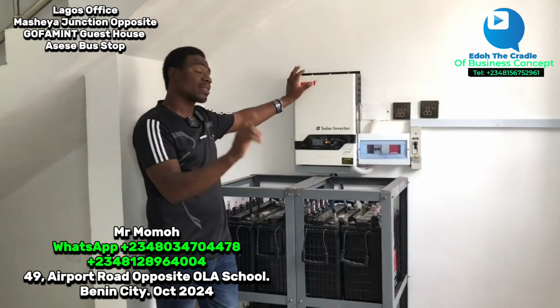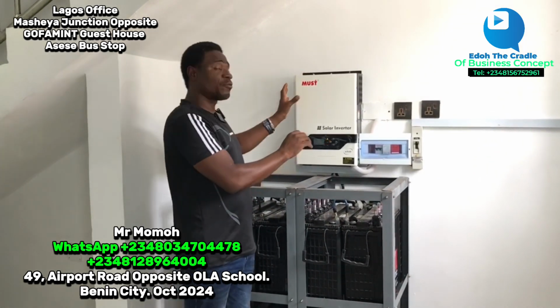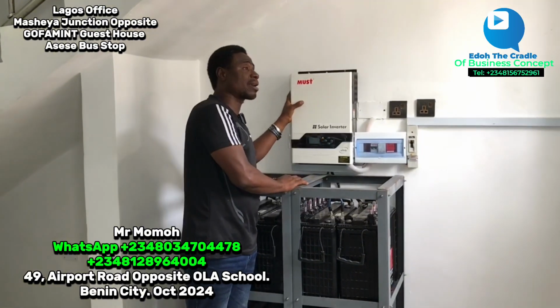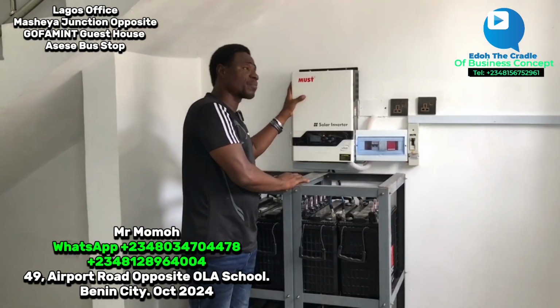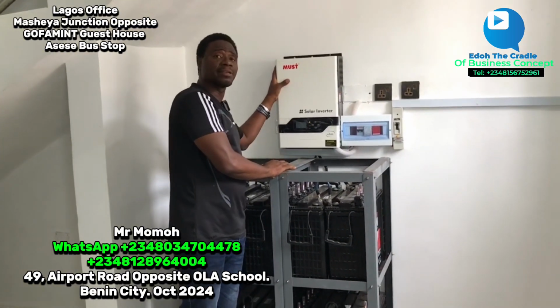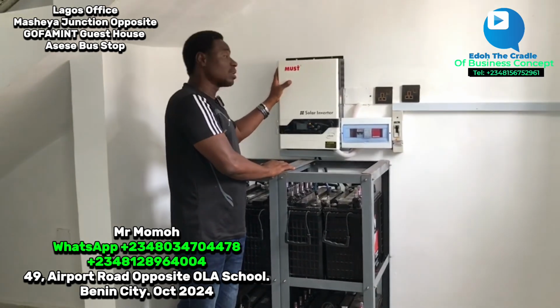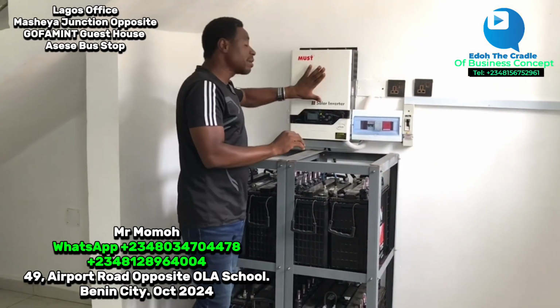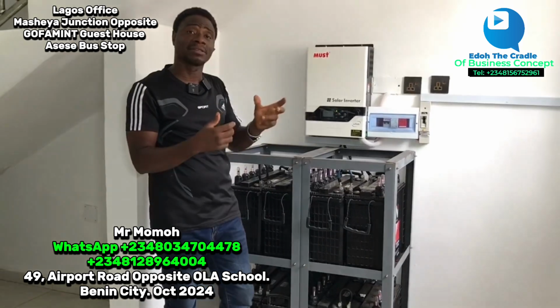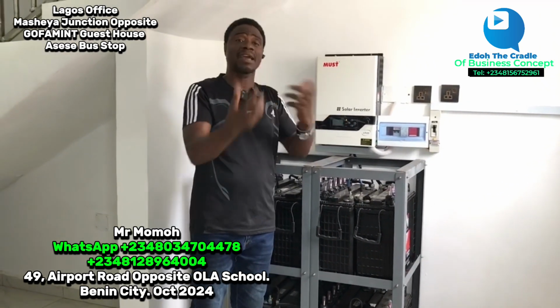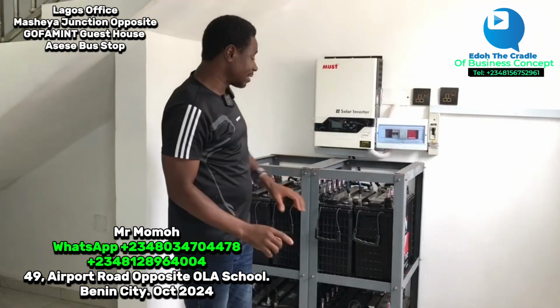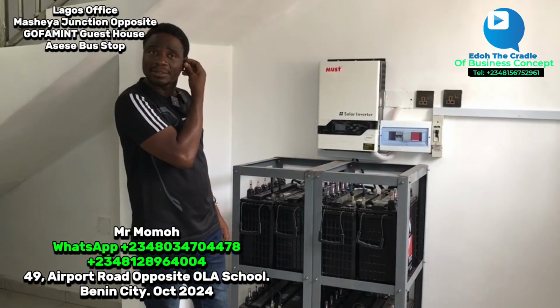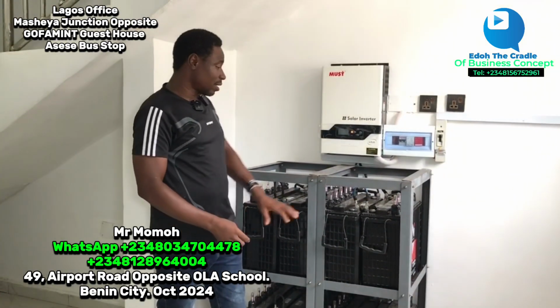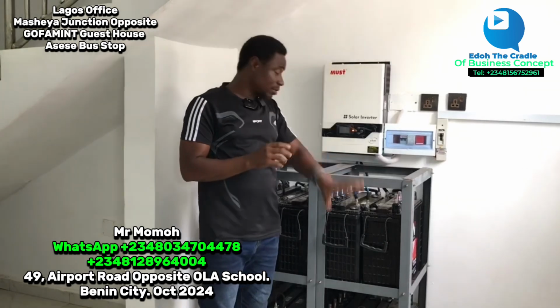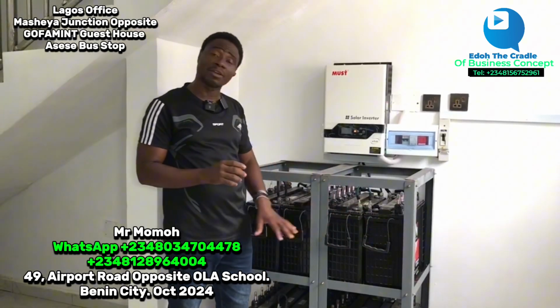The reason is simple logic: if we tell you this 5 kVA right now can carry 3 AC units, ideally if you put 3 AC on this 5 kVA, it can power them, especially when it's an inverter AC. But the truth is that 4 batteries cannot withstand that load. It's not possible — I talk about 3 AC, but these 4 batteries cannot withstand it.